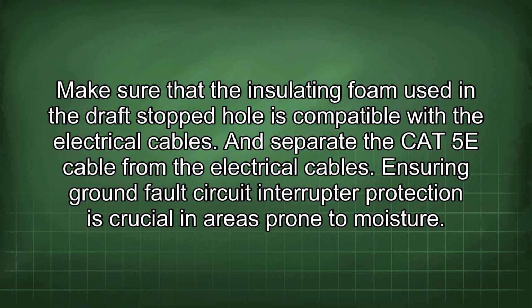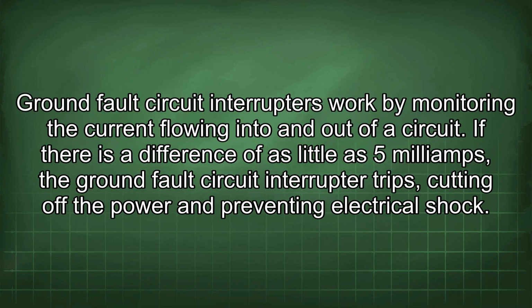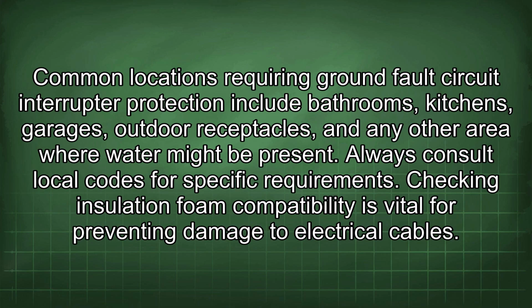Ensuring ground fault circuit interrupter protection is crucial in areas prone to moisture. Ground fault circuit interrupters work by monitoring the current flowing into and out of a circuit. If there is a difference of as little as 5 mA, the ground fault circuit interrupter trips, cutting off the power and preventing electrical shock. Common locations requiring ground fault circuit interrupter protection include bathrooms, kitchens, garages, outdoor receptacles, and any other area where water might be present. Always consult local codes for specific requirements.